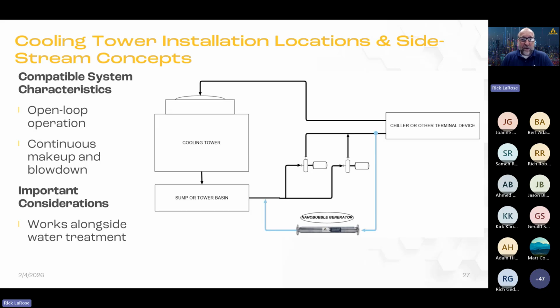This is the way we've been installing them on cooling towers this year. On the left you see the tower in the sump basin. This is very basic - your system will be more complicated - but from a basic standpoint, we just install them on the condenser water loop using the differential pressure between the discharge and suction side of the pump. That's the simplest and easiest way to do it. There are other ways to pipe these, and this is just to wet your whistle.